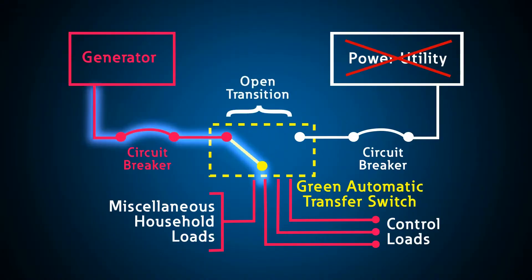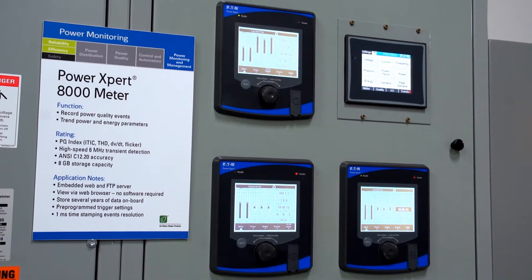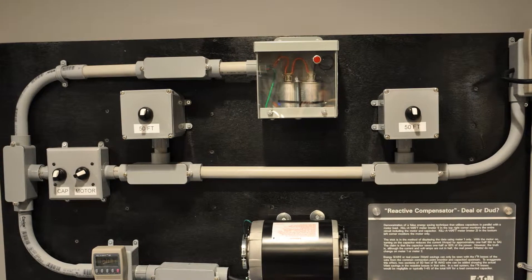Issues like voltage flicker and misoperation of the TVs and computers are obvious when we create these scenarios. While the resi room may simply look like a break room, it has significant importance here at the PSEC. Several of our residential products were designed and tested with significant utilization of the resi room. This green transfer switch was in development for about two years, and the engineers spent many weeks at the PSEC for alpha and beta testing. Like the resi example, we've done significant beta testing for some of our other product lines, giving meaningful feedback on beta units to tweak designs prior to final release. Finally, one of our favorite things to do is debunk false energy saving claims by testing these magic black boxes that have flooded the market recently — demystifying what is real and what isn't as far as energy savings goes.